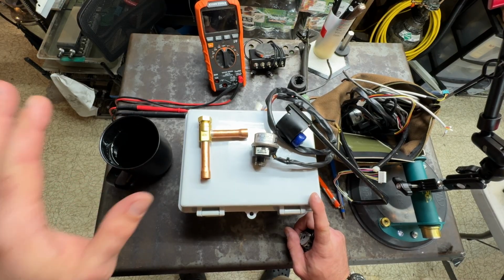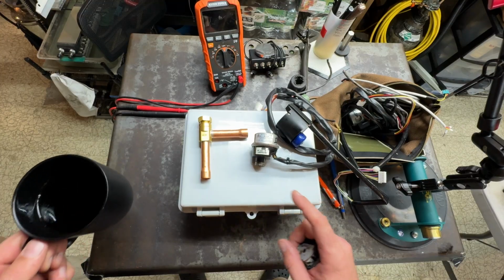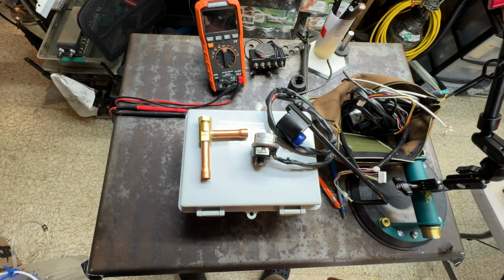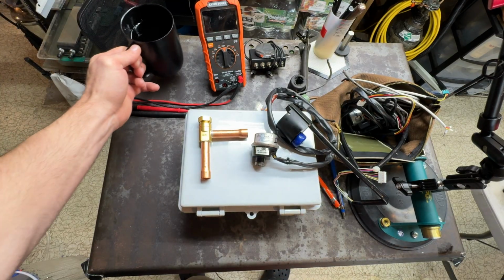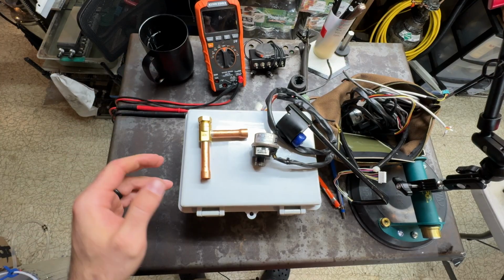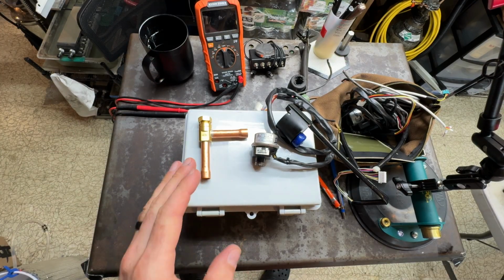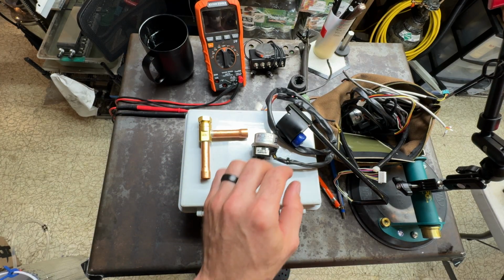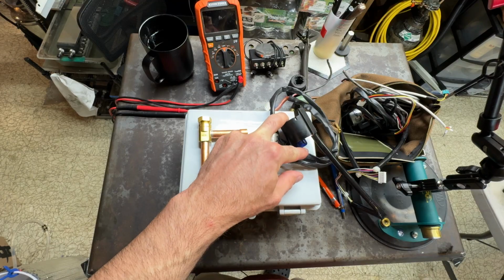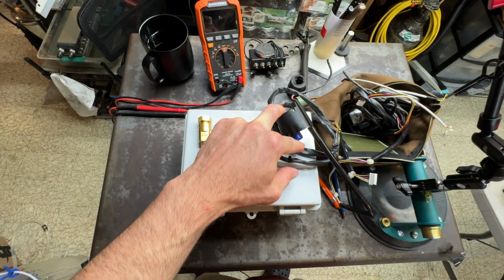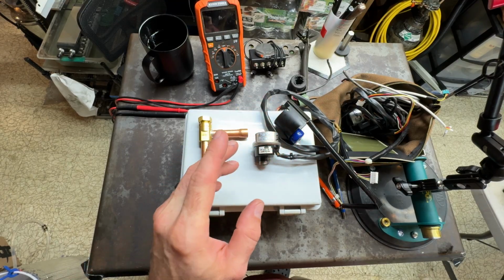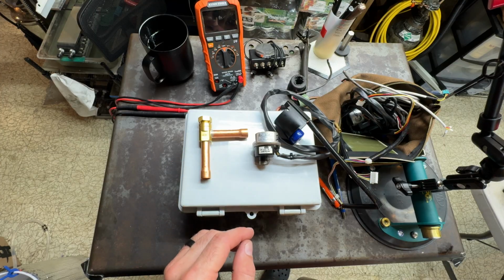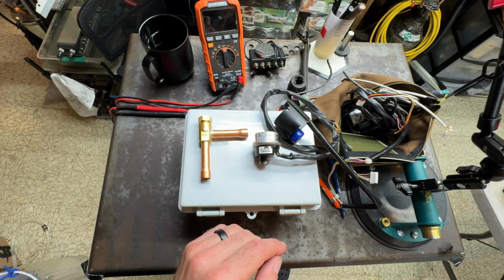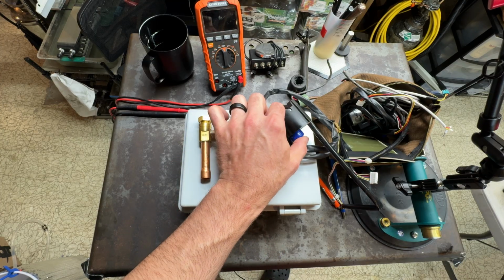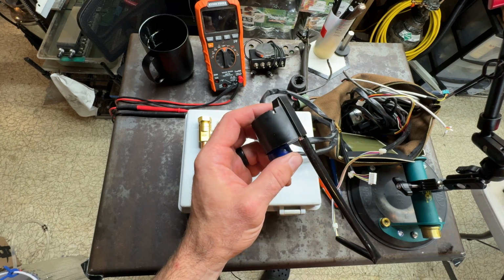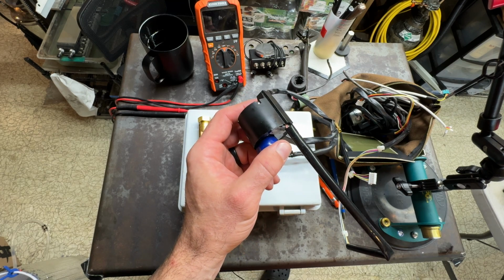So one of the things you need to be doing on a PM is checking your EEVs. If an EEV fails on an indoor unit, that's pretty easy to diagnose. But if something like a subcooling EEV or a main EEV on an outdoor unit fails, that can get tricky. Now a real good Daikin guy, and I've worked with some of the best in the world...